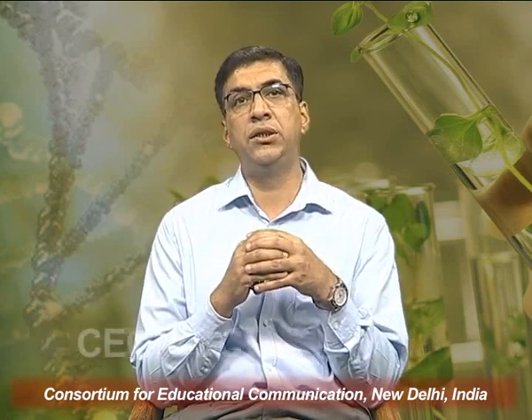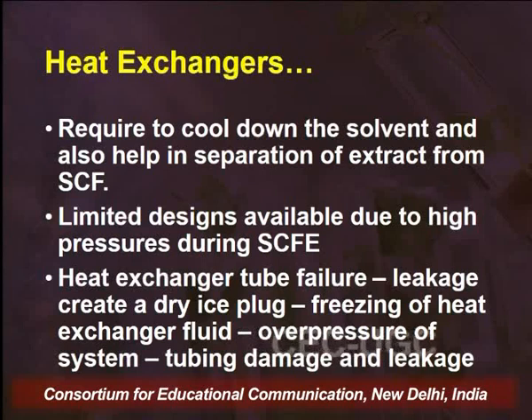But whatever exchangers are there, every design is a proprietary design that is being manufactured by the manufacturers. Now, as I highlighted, heat exchangers are very critical in the supercritical fluid extraction unit, because if there is any kind of failure in the function of the heat exchanger, it may lead to certain problems in the extraction unit. Like if there is any kind of leakage of the temperature from the heat exchanger, that is, they are not able to maintain the temperature, it may create certain ice plugs in the unit.